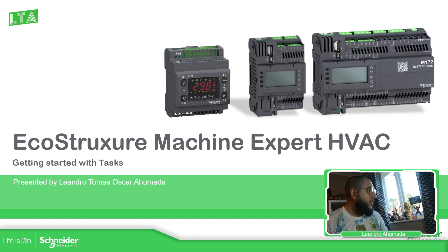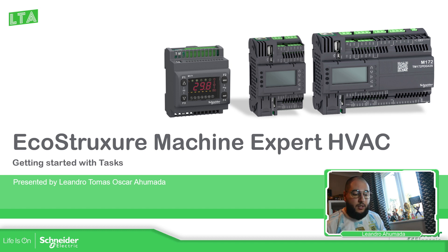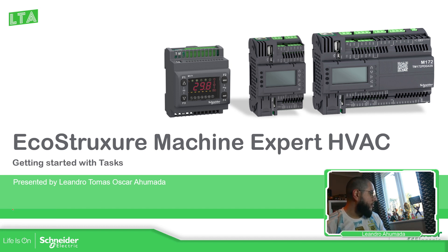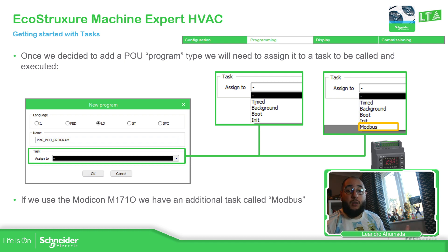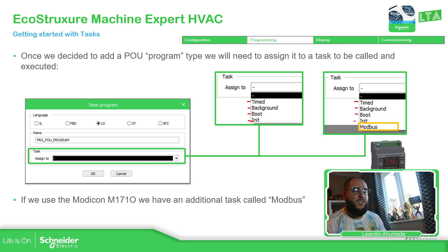Inside the controller, whether it's the M172 Performance Optimize or M171, we have different tasks. The tasks are the place where we put our POUs programs to run. On the M172 we have: time, background, boot, and init. On the M171 Optimize we have the same tasks, but we also have one specific task for Modbus — which is where we call the Modbus function to be executed on the M171 Optimize.